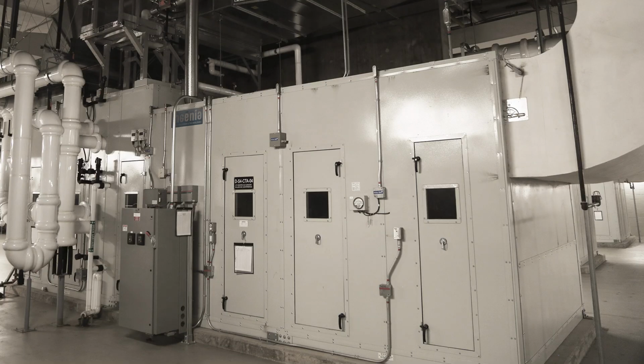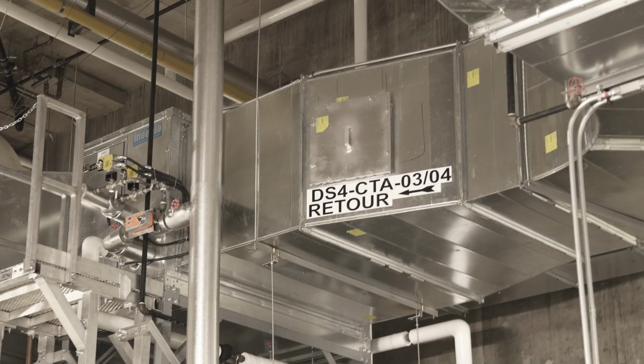So when we're thinking about placement of a humidification system, how does that placement influence the overall setup of our air handler? Yep. So if we go back to our example, if there's a boiler, okay, they've already got the boiler. You don't need any extra pieces other than you need to disperse the steam. And so then you think through, where could I apply the steam? And steam doesn't dissipate immediately. Having it in an even airflow is an important piece. So doing that potentially in an air handler where it's going to distribute to all the different spaces in a building, or if you just want a specific space, then you're into a branched piece of ductwork as an example.